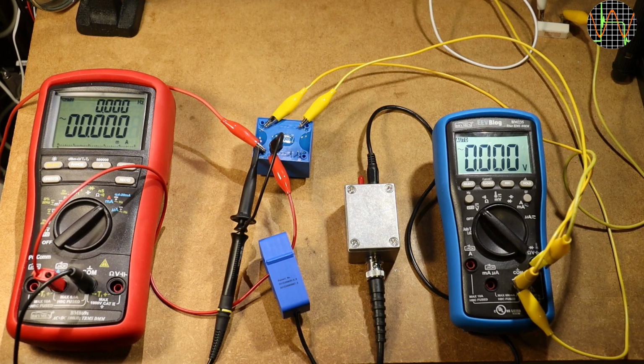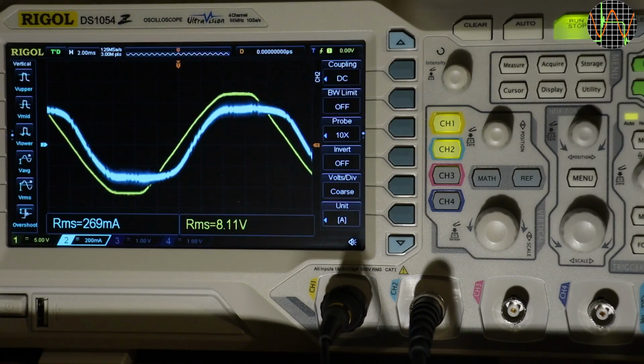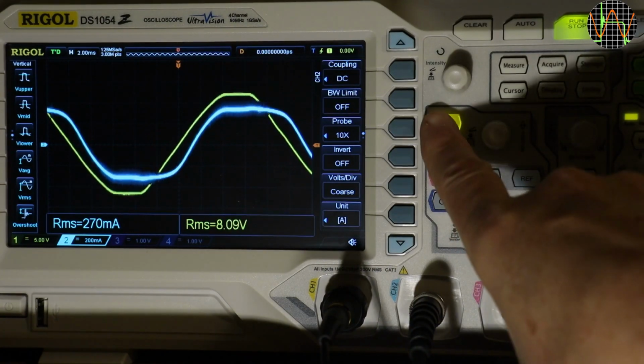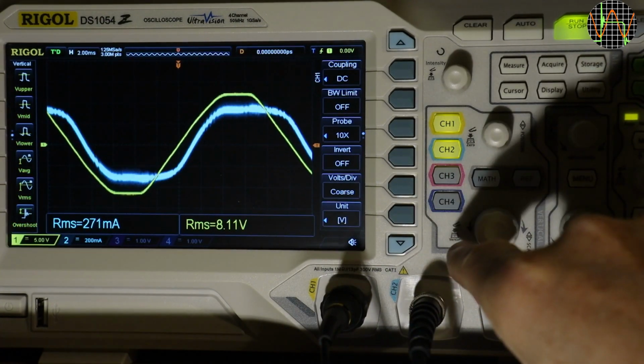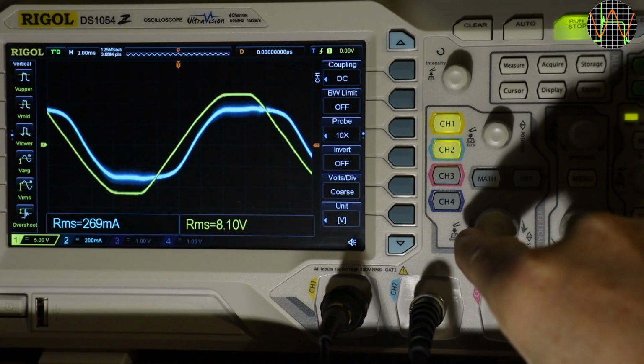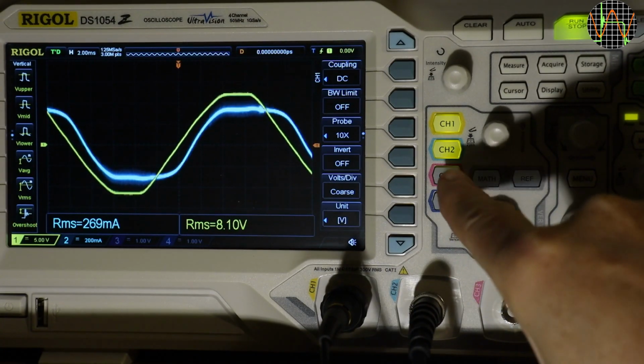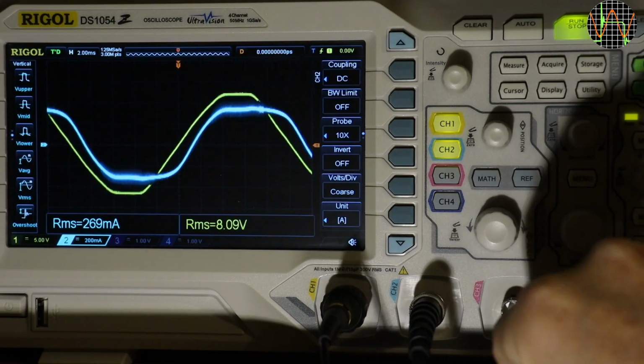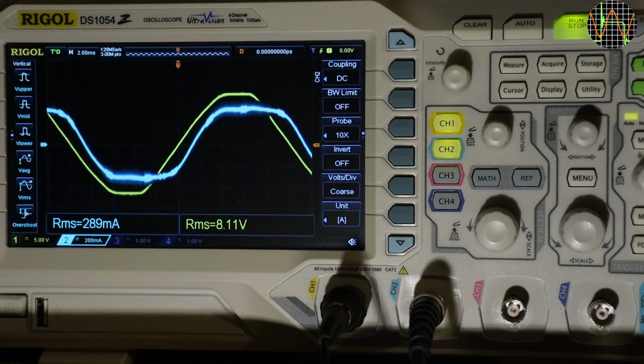The mains transformer is that squarish blue box. The high voltage primary side are the yellow test leads. We see a current of about 270 milliamps on the secondary side. On the scope, we see the voltage on channel 1 in yellow and the output voltage of the current transformer in blue on channel 2. It's quite cool that although it's a voltage, of course, you can tell the scope it really is a current, and it then shows the current measurements and scale indicators.